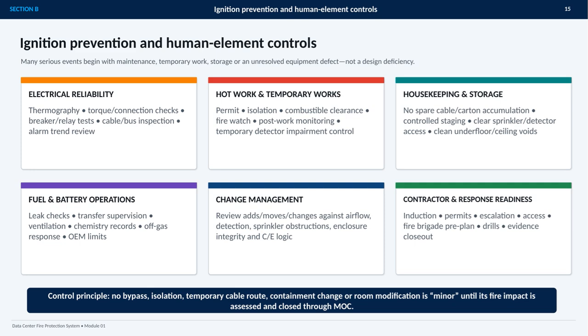Electrical reliability depends on thermography, connection and torque checks, breaker and relay testing, cable and bus inspection, and alarm trend review. For hot work, controls include permits, isolation, combustible clearance, a dedicated fire watch, post-work monitoring, and management of any temporary detector impairment. Good housekeeping means removing spare cable and carton accumulation, controlling staging, preserving sprinkler and detector access, and keeping underfloor and ceiling voids clean.